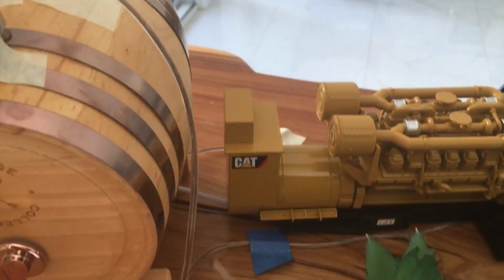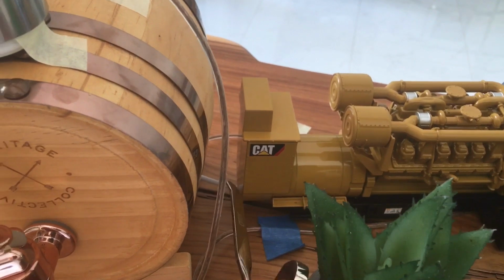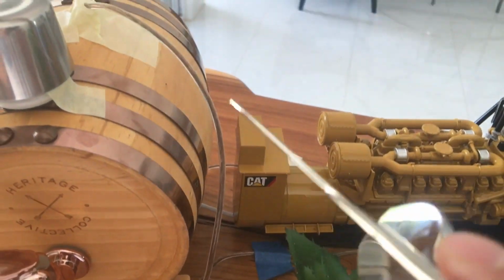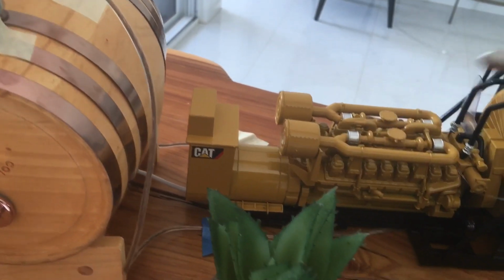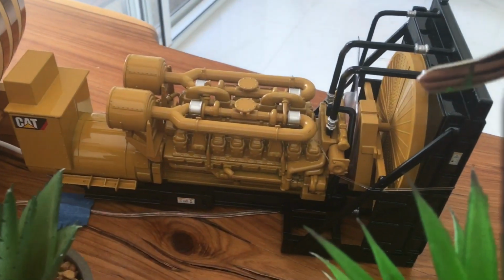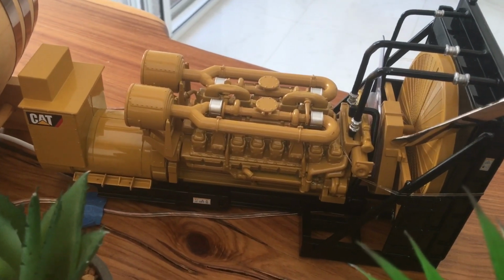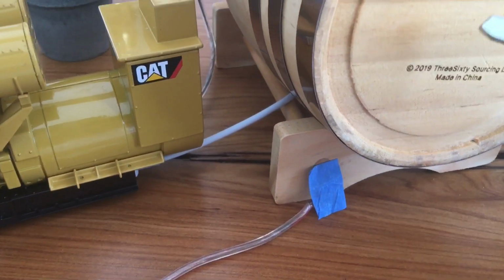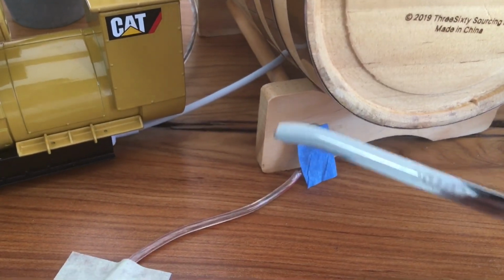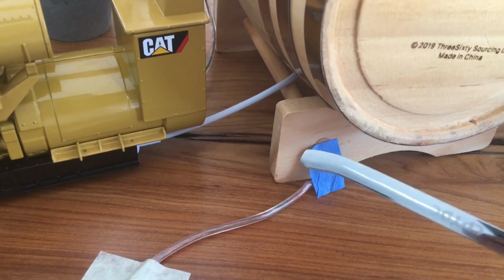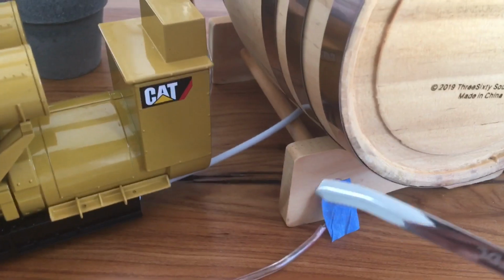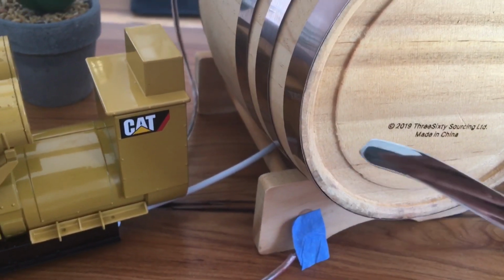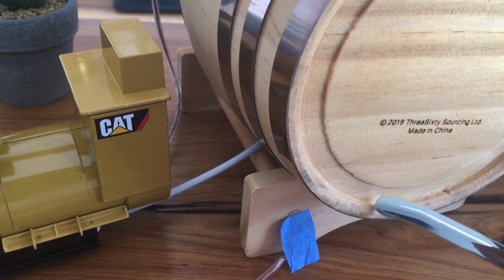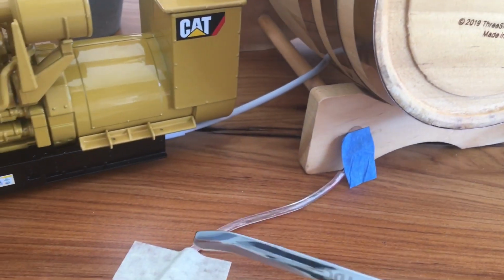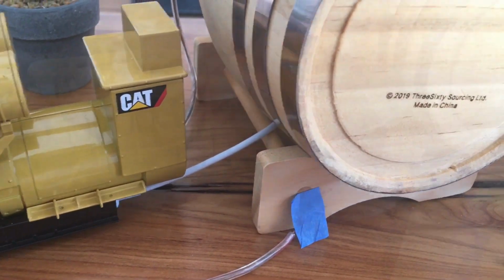For fuel you have a suction line and this is the discharge line. You need to work out a day tank to make sure your fuel flows properly. You also have fan belts here. Pay specific attention to the grounding of the fuel tank—always make sure any equipment in the fuel tank, your fuel pump, electric motor, and any piping is in the ground loop and grounded correctly.